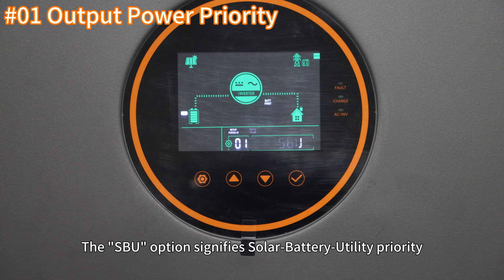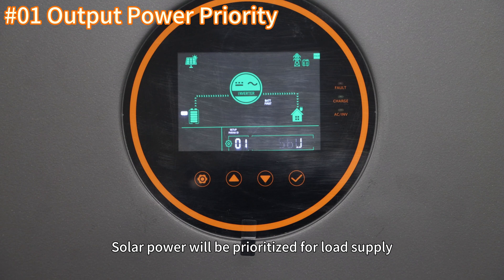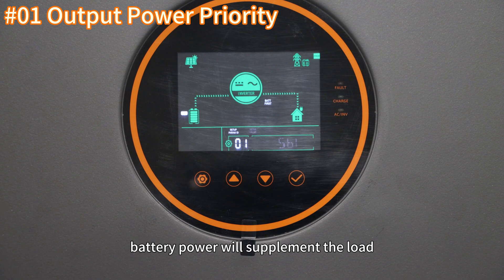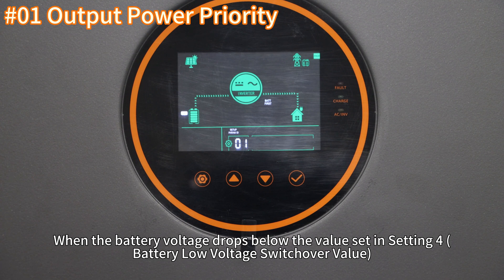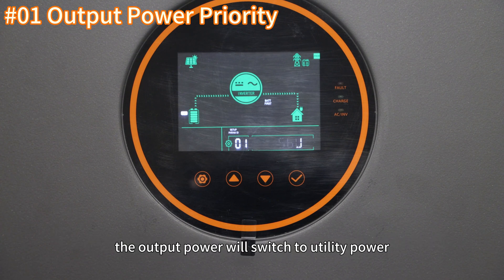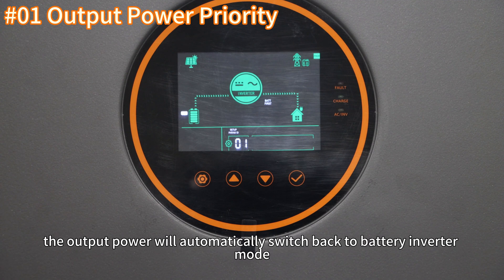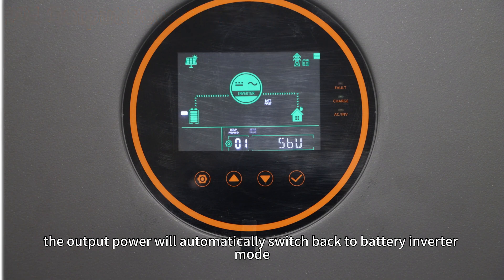The SBU option signifies solar, battery, utility priority. Solar power will be prioritized for load supply. If solar energy is insufficient, battery power will supplement the load. When the battery voltage drops below the value set in setting 4, the output power will switch to utility power. When the battery voltage rises above the value set in setting 5, the output power will automatically switch back to battery inverter mode.